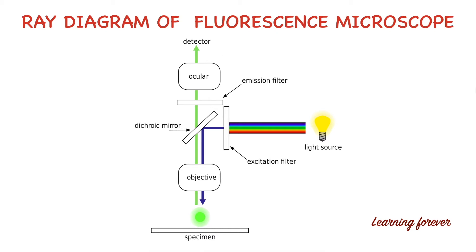Now let's see how the fluorescence microscope works. First, the biological sample or microorganism is mixed with fluorescence dye. After mixing, the sample is placed on the stage of the microscope. Light is then illuminated by the light source, consisting of multiple colors. The excitation filter, kept between the light source and the dichroic mirror, blocks all other colors and transmits only blue light. This blue light is then reflected towards the sample by the dichroic mirror.